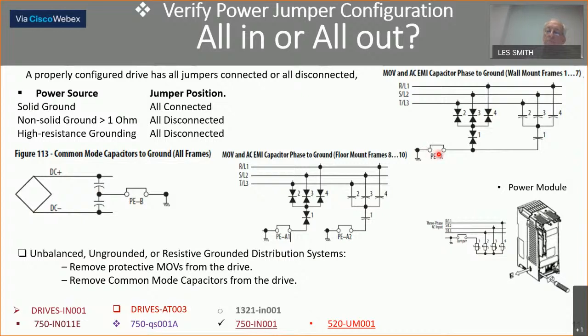And in the old days when we had the older drives, this MOV would be bigger than the others. And if we did have an ungrounded system and we sensed problems, we would take some side cutters in there and clip that wire. That would be a bigger MOV than the other ones. But anyway, that's your wiring. So these are both in or both out.